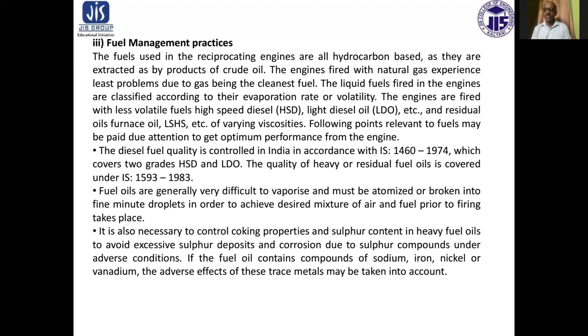If the fuel oil contains compounds of sodium, iron, nickel, or vanadium, the adverse effect of these trace metals may be taken into account. Viscosity of fuel plays a major role in optimizing the performance of the engine. If the viscosity is too low or too high, the droplet size, spray pattern, and so the consumption and fuel efficiency would vary. Too low viscosity introduces excessive wear, whereas too high viscosity results in incomplete combustion besides frictional losses and increased load on the fuel pumping system. With viscous oil, it is necessary to reduce the viscosity before it can be atomized. This is achieved by preheating of fuel to an appropriate temperature to obtain the required viscosity at the injector tips.